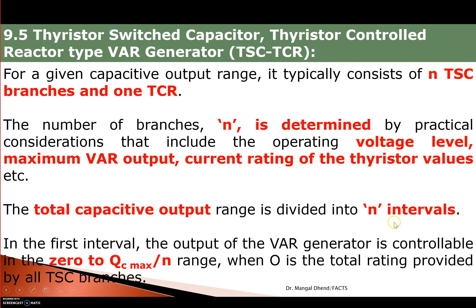The total capacity output range is divided into N intervals. In the first interval, the output of the VAR generator is controllable from 0 to QC_max divided by N. For example, if total KVAR is 40 and N is 4, each interval is 10. So the first TSC bank supplies 10, the second from 10 to 20, the third from 20 to 30, and the fourth from 30 to 40. From 0 to QC_max over N, the range will be variable power.